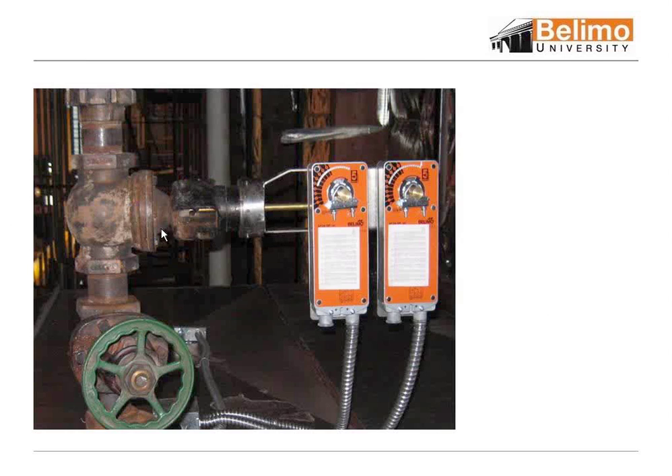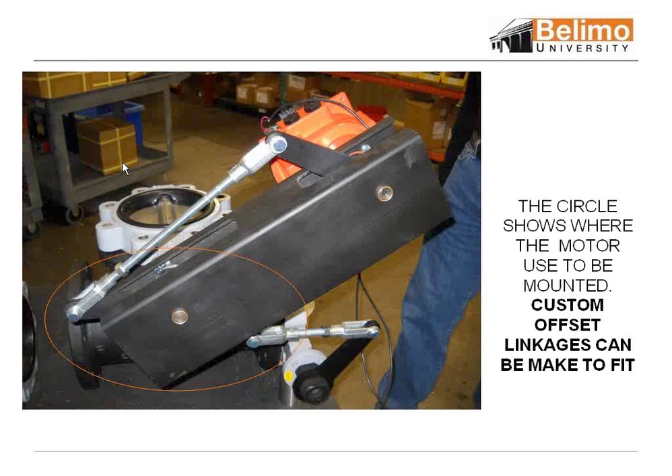As you can see, there's an old globe valve. We did a retrofit. If the valve's integrity is good, why change it? But most of the time, if the valve's older, you may want to think about changing the whole valve. Here's an example we just set up — it was a pneumatic application, and because of room constraints, we weren't able to put that SY actuator right on top of the valve. These are just examples to show you that Belimo will think outside the box to retrofit applications.